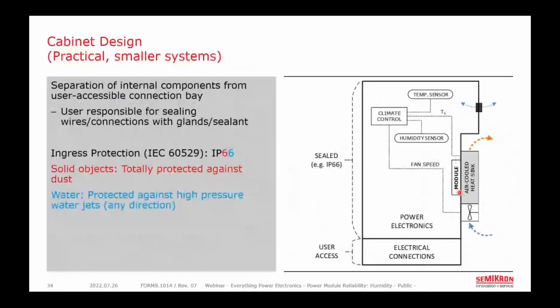Now, for smaller systems, let's say outdoor power converters in the 100 or 200 kilowatt range, or maybe even smaller, what we're seeing a lot of manufacturers doing is sealing the box containing the power electronics and then adding a small hydrophobic membrane vent here.